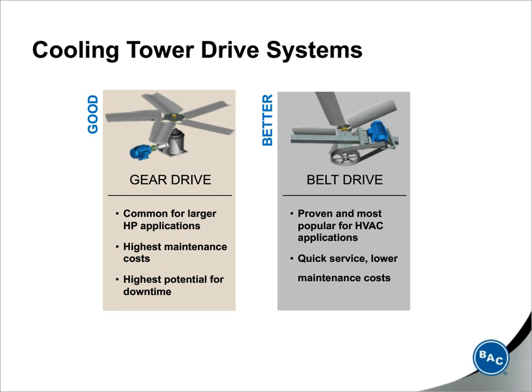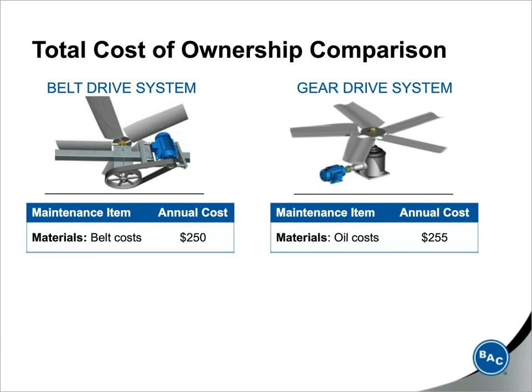Gears still do have a place on some of the largest motors, for instance, on 100 horsepower applications, where it's a more practical solution at that particular size, but gears do have higher maintenance costs, and they have the potential for extended downtime. They also have greater environmental impact because of oil change requirements. So let's look at the costs of both the belt and gear drive system in terms of labor and materials. When you compare labor and materials, belts really are going to win every time. The material costs you can see here between belt and gear, it's really a wash. They're about the same.